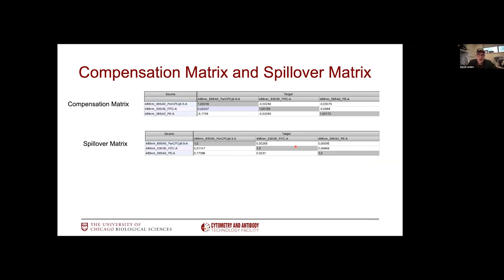All these compensation values are stored in a compensation matrix. That is basically what the software will use to inform how to deal with the raw data and deal with the spectral overlap in your assay. Later on, this compensation matrix is inversed and transformed in a spillover matrix. That will tell us the level of spillover between the different fluorophores. These two, the compensation matrix and the spillover matrix, are sometimes used interchangeably, which causes confusion.